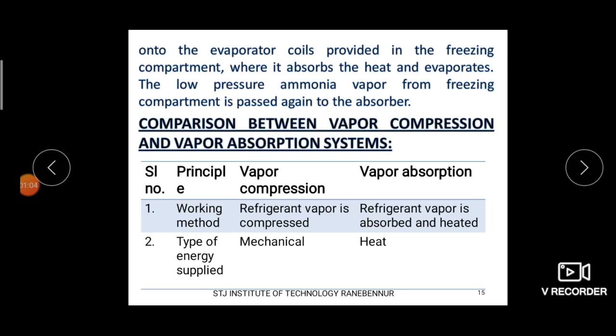In case of vapor absorption refrigerating system, the refrigerant vapor is first absorbed. In the VAR system, we make use of one absorber — inside that absorber, the absorbent will absorb the vapors of the ammonia, forming what we call a strong ammonia solution. In the heater-cum-separator, we make use of one heating coil in order to heat that strong ammonia solution to get vapors of the ammonia.